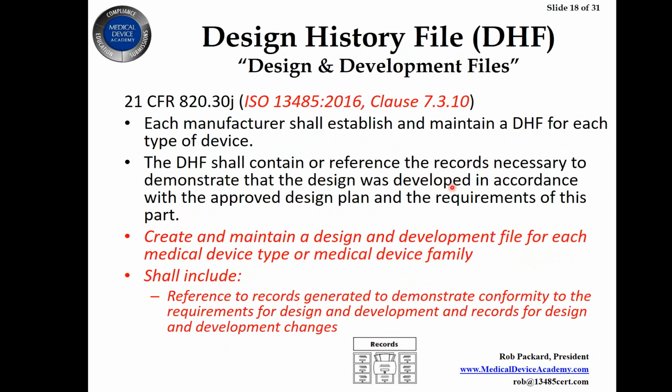But if you have significant differences, particularly in intended use for the products, they probably shouldn't be part of a family. We have the same thing happen with CE marking technical files. Companies want to group as many products as they can into one technical file. But if you have a different clinical evaluation for the products, you have a different IFU for the products, and a different risk management file for the products, you probably don't have a strong case for grouping them together as a family. So that's something you have to keep in mind.